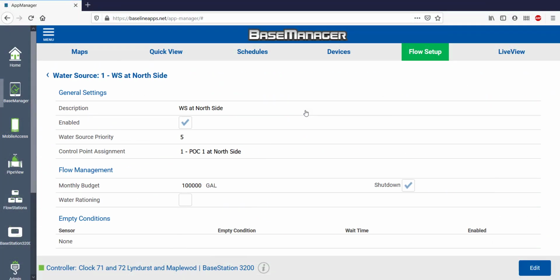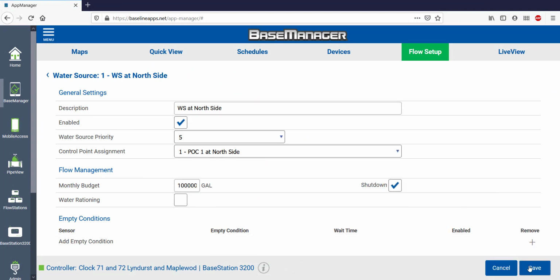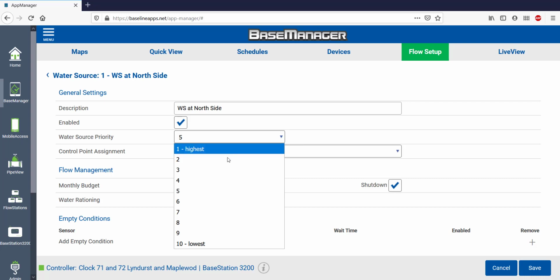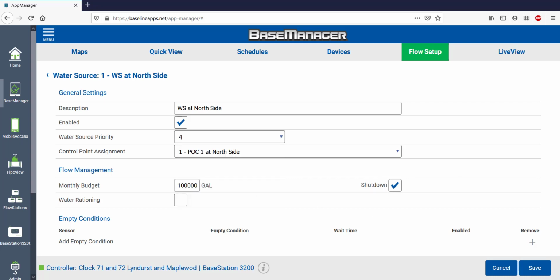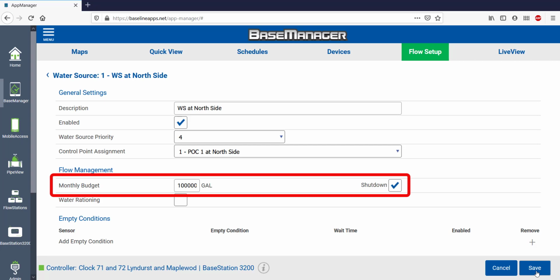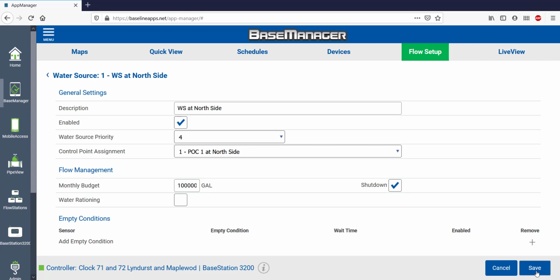Go back to water source 1 and select Edit. The only change we're going to make is at water source priority. I've changed it to priority 4, higher than priority 5 in the other water source. Now it will use water source 1 exclusively until it's disabled or shut off. Earlier I set a 100,000 gallon monthly budget and selected shutdown. When it exceeds that budget, it will shut down water source 1 and automatically switch over to water source 2.